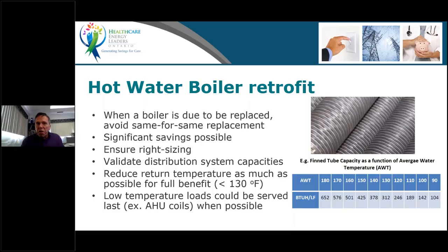So if your long-term care facility or your hospital was designed to supply 180 degree water, and all the baseboard and all the coils are high temperature, you're going to put a condensing boiler in there and you won't be able to run at the temperature required for condensation. You'll be running very often at 160, 180 Fahrenheit. It's all in Fahrenheit, I'm not very good in Celsius here. And that means you will not achieve the promised savings. You will achieve savings compared to a standard boiler, but you will not be condensing all of the year. You may be condensing when the load is lower, but not when the load goes high. So be very careful about that.